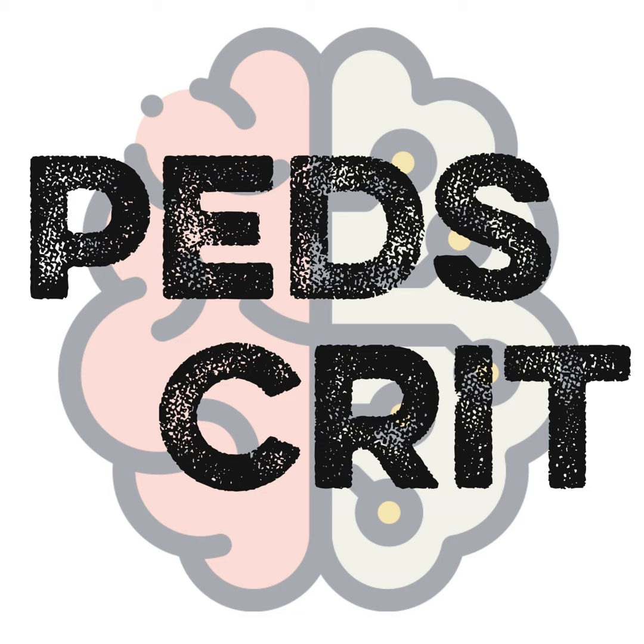Nice. Do you ever find yourself needing to, and this might depend on the brand you use, whether it's Servo, Avea, Bella Vista, swap out the flow sensor physically? I have not come across that, where we're specifically trying to swap out the flow sensor. There have been times where we make all the adjustments that we think we need to make, and we're just not making it, and we'll swap out the entire ventilator. It's not for a different brand, it's just for a different one. And then pull the ventilator away from the bedside and let us go through a more significant troubleshooting. So there are times where we will do that, and that seems to help. Instead of making the patient suffer through us doing all our troubleshooting, we'll pull the ventilator separately and try to figure out what's going on.